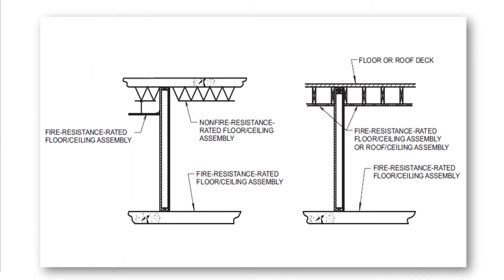Supporting construction, this is something that seems to be forgotten often, and this isn't just for fire barriers, this is for all rated assemblies. When you have a rated assembly, whether it's the walls or the horizontal assemblies, whatever's holding that up, the supporting construction needs to be rated the same as what that assembly is required to be rated at. But have the conversation with your structural. Sometimes you've got bracing that may be there for structural requirements for movement, but if you lose that bracing in a fire, you wouldn't lose the wall. But you've got other types that if you lose that bracing, it could be holding up that wall. And if you lose it in a fire, you're going to lose that wall. So have the conversation with your structural as well to make sure you are rating what needs to be rated. Don't forget the supporting construction.